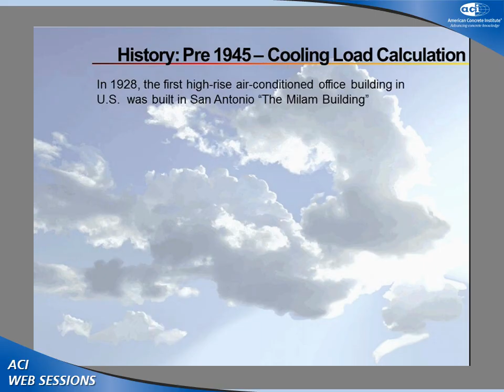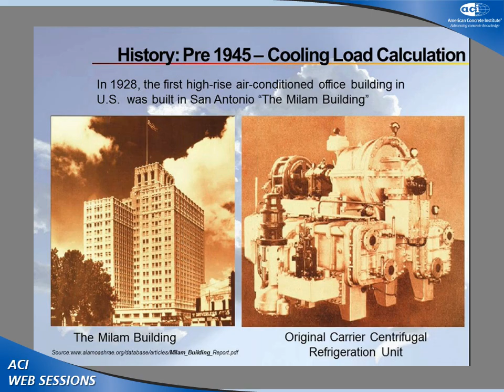In 1928, the first high-rise air conditioning was built in San Antonio, the Milam Building. It was a custom job by the Carrier Company, a large office building of about 200,000 square feet, with 11 air handling units, one on every other floor, and roughly a 300-ton system, about the size of the Missouri State Building.